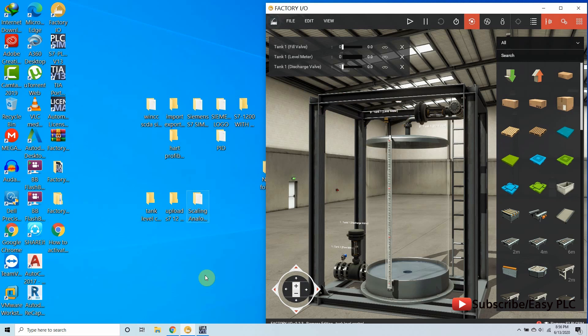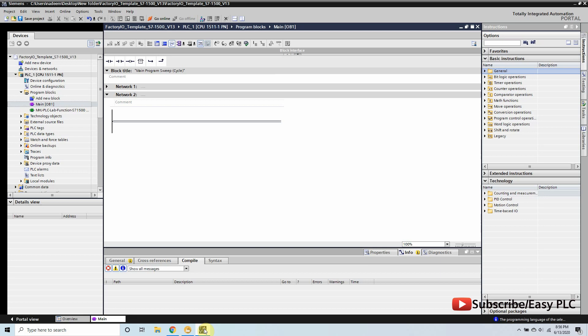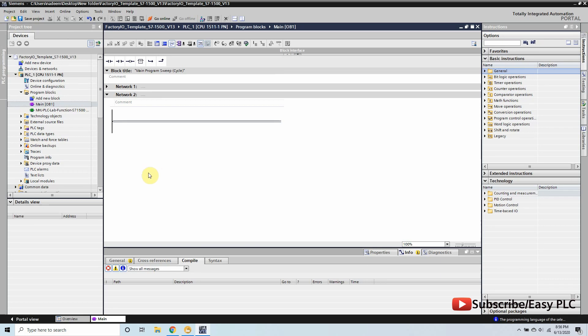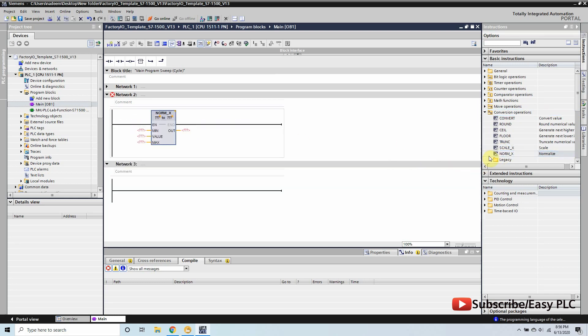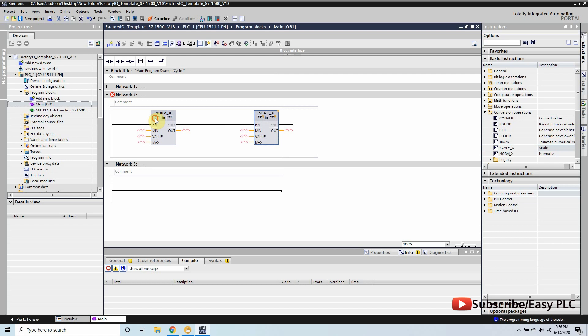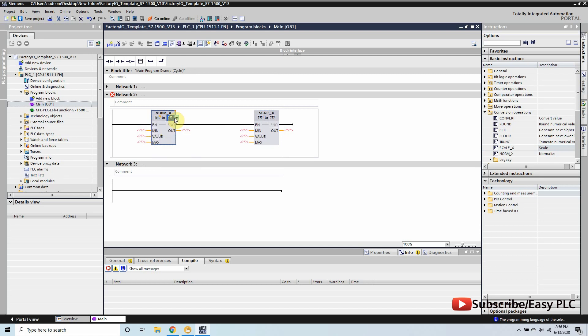Now we will go to the TIA Portal and do some programming. In network two we make the analog scaling logic to convert the analog signal coming from the sensor to 0 to 100 liters using NORM_X and SCALE_X instructions.